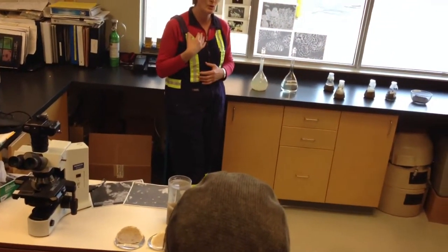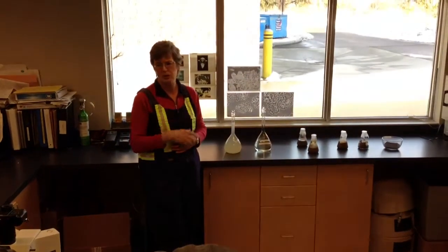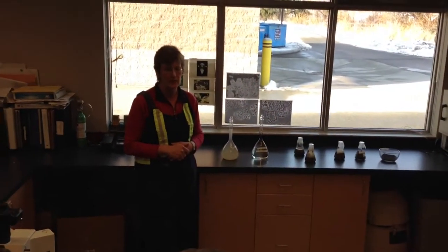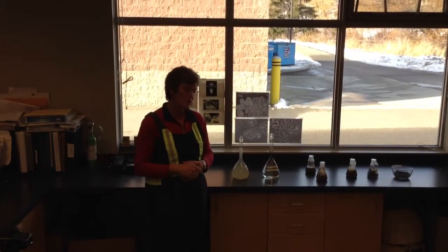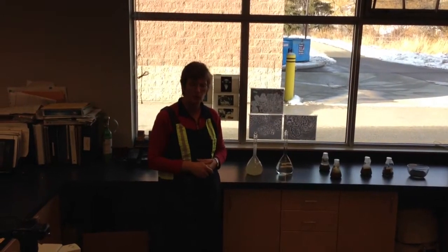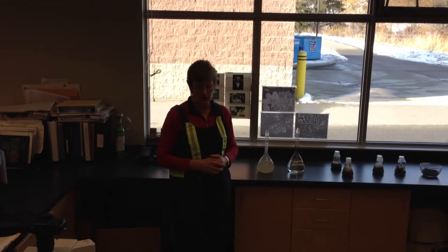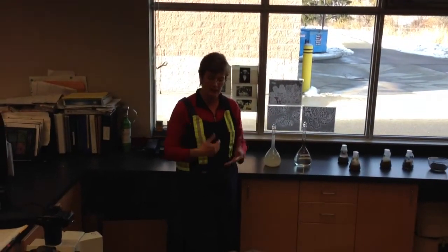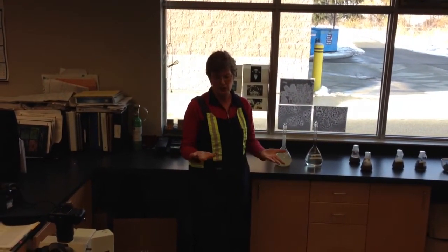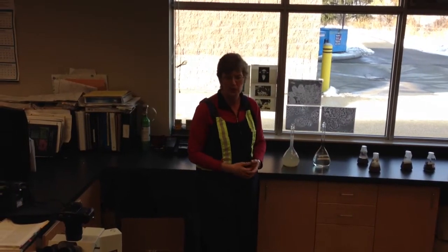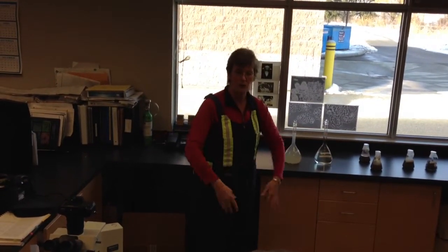So even though we don't discharge to the lake, we still regulate, or we try to meet a lake quality effluent. So we hope that the bacteria will remove the phosphorus and the nitrogen. So that's in the bioreactor. After they have grown and are happy and are eating, eventually we have too much of them. So we have to get rid of these solids because as we are feeding them, we're always making more.